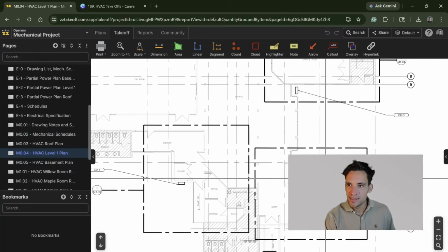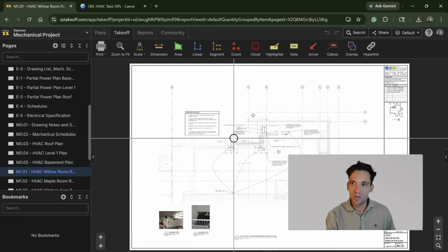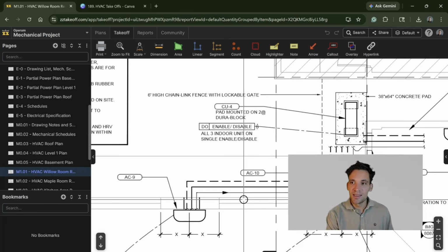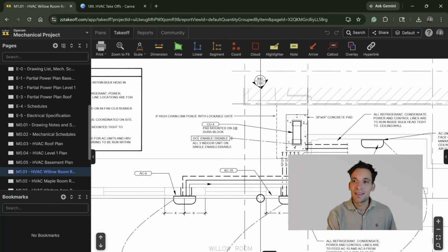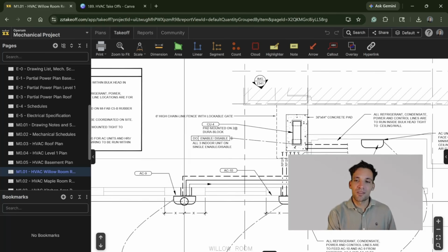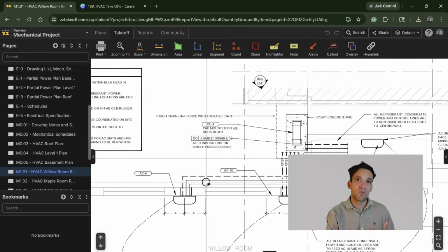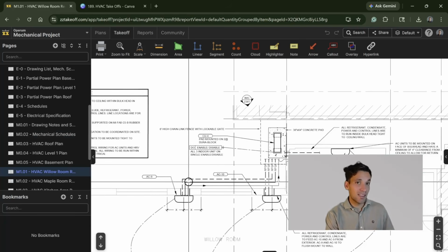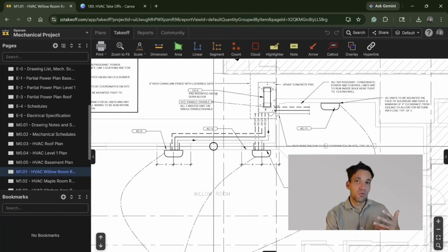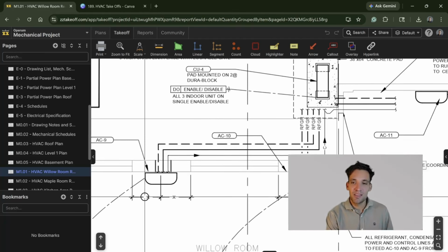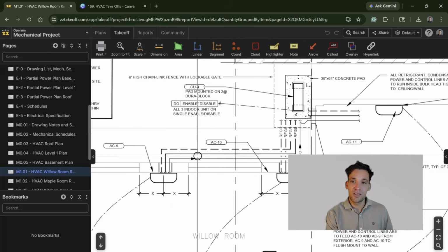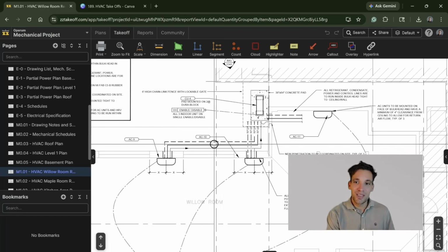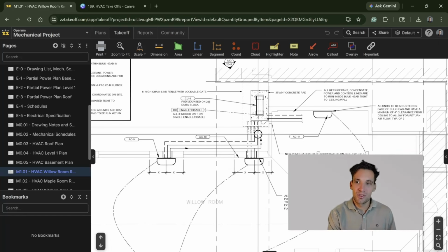Another thing worth noting is that, again, it depends a little bit on the purpose of the takeoff, but if we're talking about condensate pipe, which might be a couple of dollars a meter, this sort of minor consumable installation, I would not go and do linear measurements of all of these items. I would include that in the assembly for this specific AC unit. Because at the end of the day, whether you're doing this for procurement or to prepare an estimate, at the same time someone goes and installs this, they'll also install that refrigerant line. So it doesn't really make sense to get detailed linear measurements of each of these individual items.